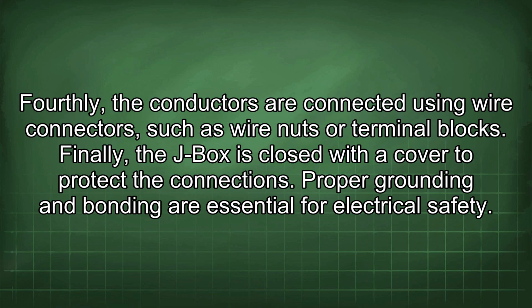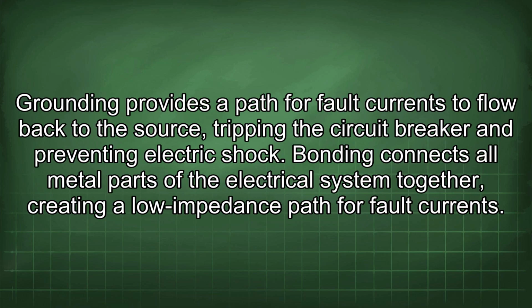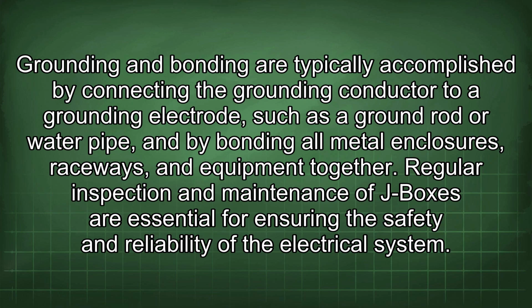Proper grounding and bonding are essential for electrical safety. Grounding provides a path for fault currents to flow back to the source, tripping the circuit breaker and preventing electric shock. Bonding connects all metal parts of the electrical system together, creating a lower impedance path for fault current. Grounding and bonding are typically accomplished by connecting the grounding conductor to a grounding electrode, such as a ground rod or water pipe, and by bonding all metal enclosures, raceways, and equipment together.